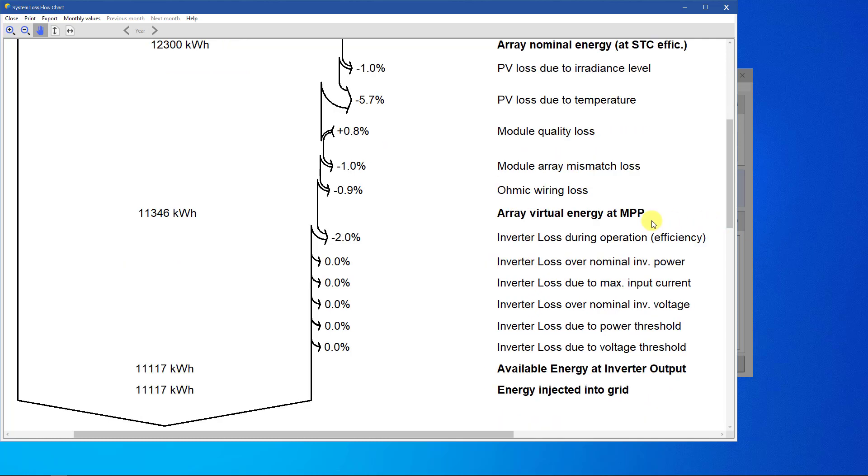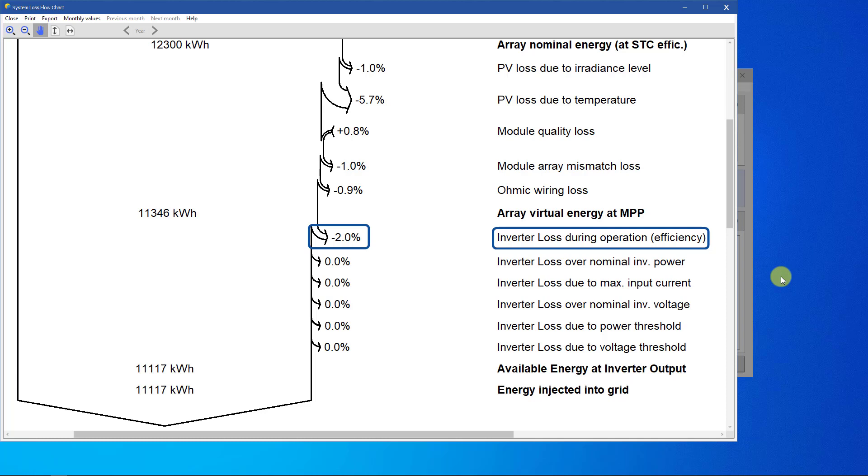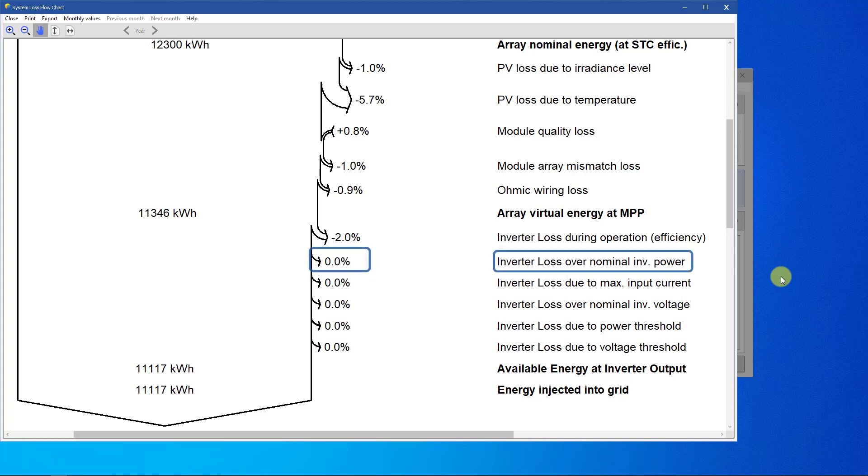Then we have losses at the inverter level. The inverter loss during operation is the efficiency loss. This is computed at each hour and depends on the power and possibly on the array voltage. If the inverter is undersized, there may be some loss due to power clipping at the nominal power of the inverter. This is called the inverter loss over nominal power and is the most frequent extra loss in PV systems.